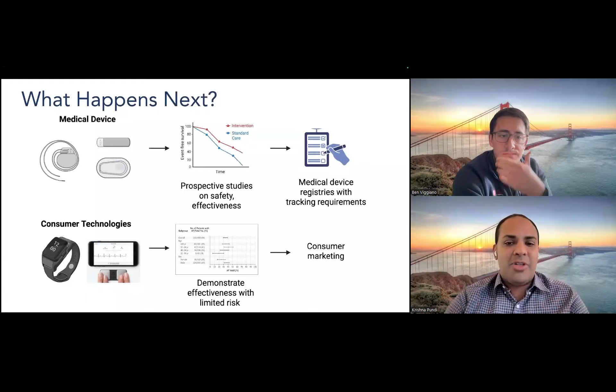And so in wearable technologies, anything that falls into the wellness realm that just allows you to live a healthy life, the FDA doesn't specifically try to regulate those things. But if you have software that you want to send through that can surface certain notifications or send advice to your users, then those things need pre-market clearance from the FDA. And so that's where most of these go through, is that the actual specific software functions are cleared by the FDA, and then you're able to actually use them in the device. But they make it clear, these aren't actually diagnoses. It's just an opportunistic way to surface a notification. Go to the next slide.